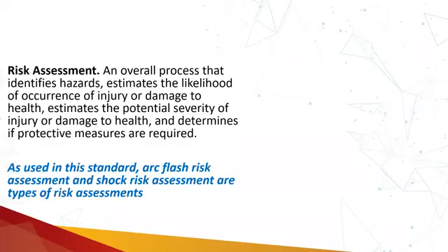What's the risk assessment? It's an overall process for identification of the hazard, estimation of the likelihood of occurrence of injury and damage to health, and estimation of the potential severity of injury or damage to health, and determining if protective measures are required or not. Here in 70E, the risk assessment is basically divided into two types. One is the arc flash risk assessment, and the other one is the shock risk assessment.